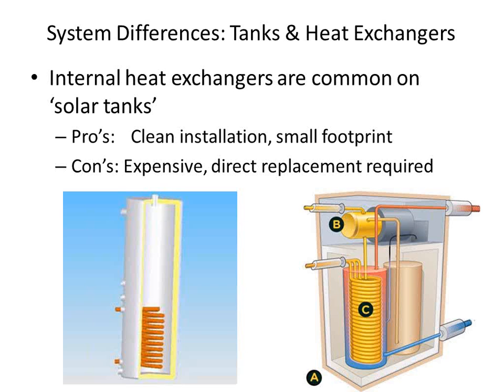If you have a glass-lined steel tank with a heat exchanger in it, when your tank fails at 8 or 9 years, that tank and heat exchanger all go out. The heat exchangers are built in, they're permanently installed, and so the whole thing goes out, and a new one has to be found. The other thing is you need to make sure when you are replacing a tank with an internal heat exchanger that you've got a direct replacement, because not all heat exchangers are the same. It's important to match the heat transfer characteristics of the heat exchanger you're putting in with the one you took out, because the system was designed to all work together.